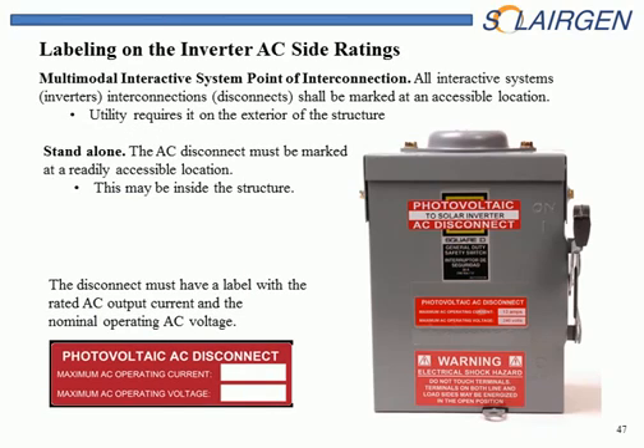So as with the interactive system, there should be an AC disconnect outside of the premises or inside the premises with a label indicating where it is. Now, if this is an interactive bimodal system, there will be at least one disconnect outside for the utility to use to disconnect because they don't trust the anti-islanding feature in the inverter. But the other AC disconnect for that backup panel may or may not be outside. It should be, and it should be labeled the same way as this is.